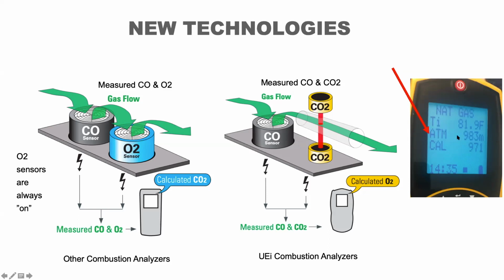This is very important because it senses the atmospheric pressure, the barometric pressure, because that affects how a non-dispersive infrared sensor works. So this is actually an internal correction. You don't need to know about it except it's there and it works. But it's been built in by UEi very thoughtfully to give you a very good CO2 level when you're doing analysis. Without that, you'd have a little bit of difficulty as you changed altitude. The CO2 level would get a little bit fuzzy, but with the built-in correction factor with the barometric pressure sensor, you get a nice stable CO2 level.